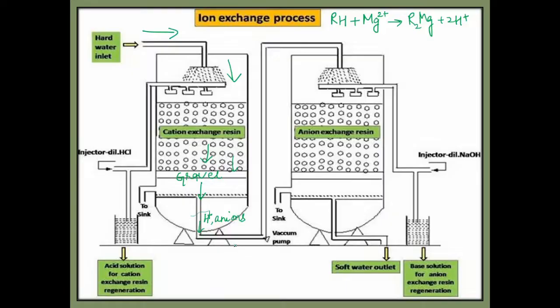Because I guess you remember that the zeolite process had only this disadvantage: it did not treat anions. That's why the ion exchange process is a better one, wherein you have one more container. So the water goes to the next chamber, and when it falls from here, the positive ions are already exchanged, you have H+ only. Now the negative ions are left.